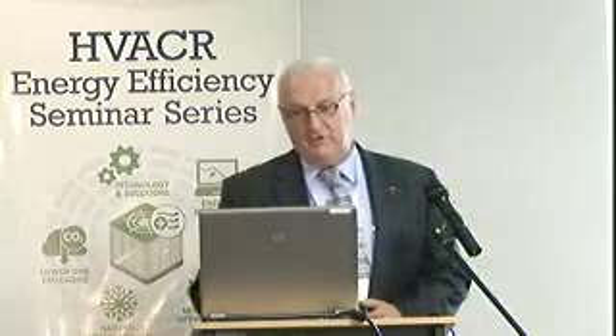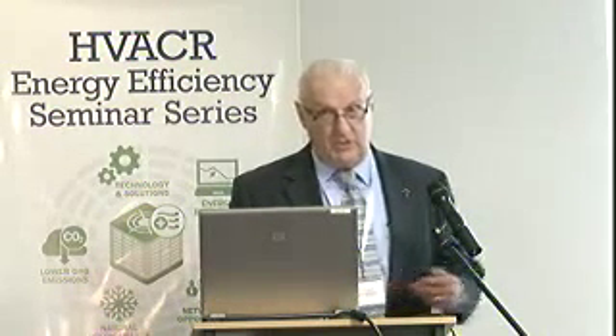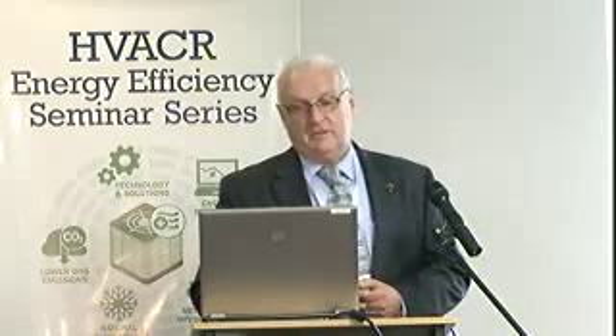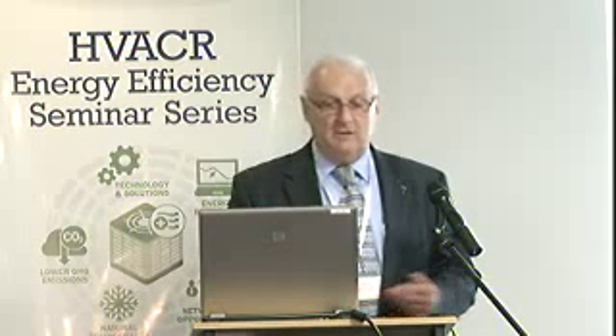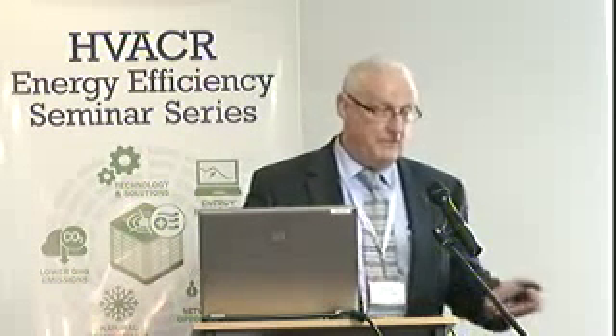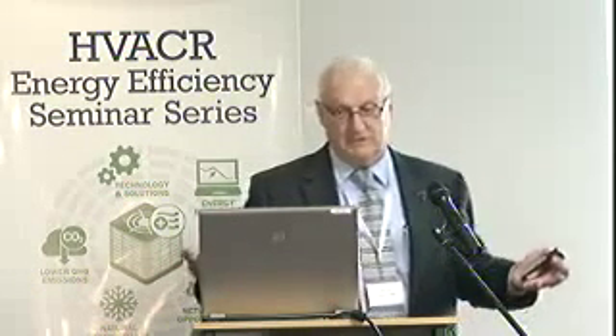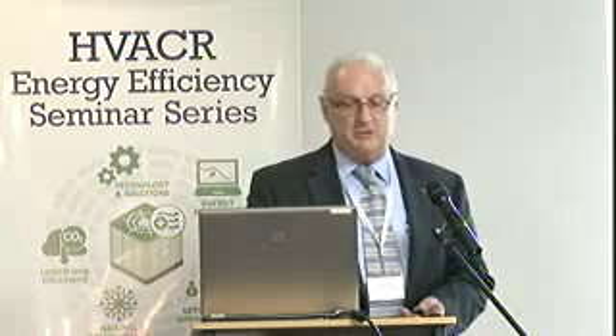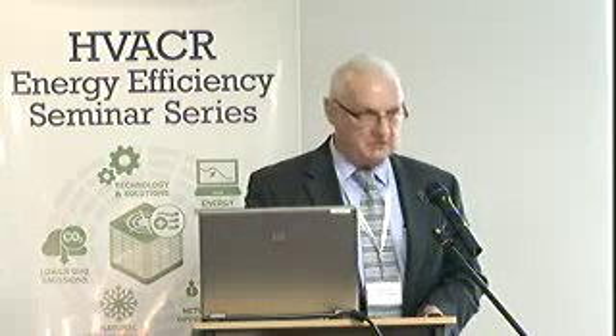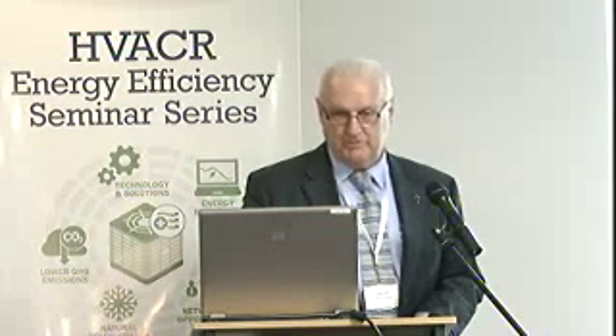Rules of thumb: HVAC and refrigeration are the sweet spot for VPO, and by that I mean you get your best return on investment out of those loads, where those loads are dominant. Saving will vary based on the design voltage for the motor and the load. As a generalisation, variable speed drives will reduce but not eliminate the level of saving for motors. Inverter air conditioning, like Daikin VRV, no energy savings. Just look at their nameplate, it even tells you on there. And as a generalisation again, electronic or switch mode power supplies, like those with IT and electronic supplied lighting, no energy savings by reducing voltage.